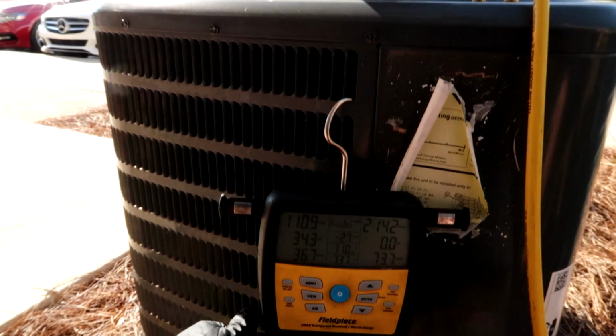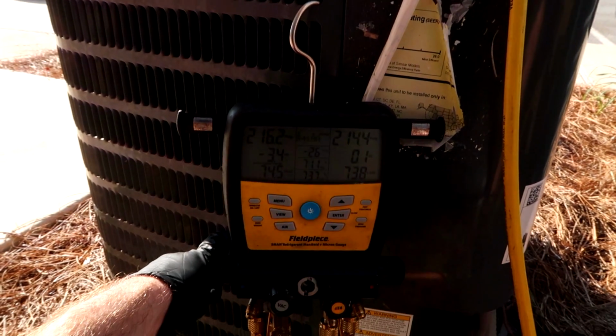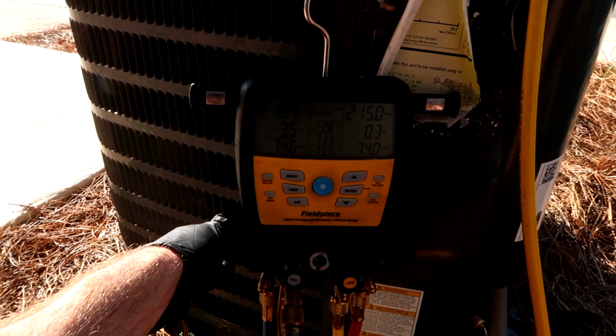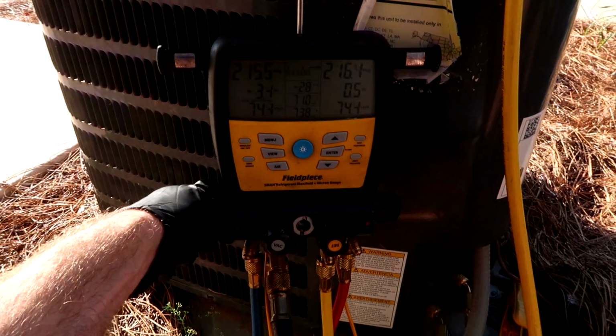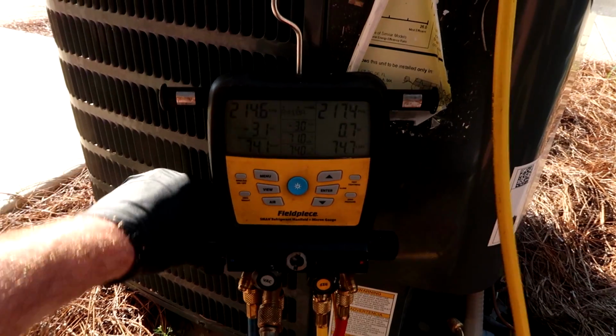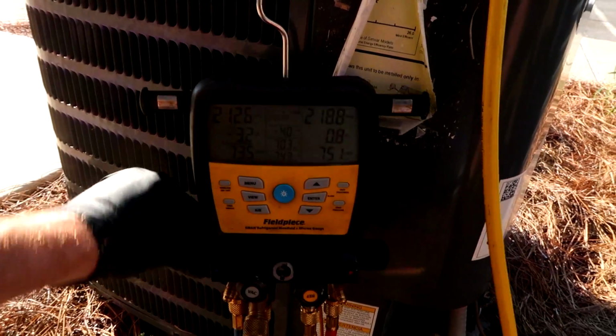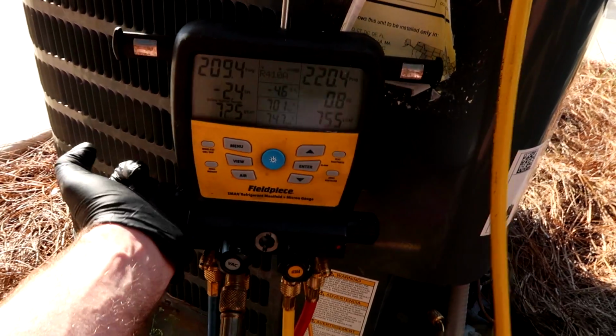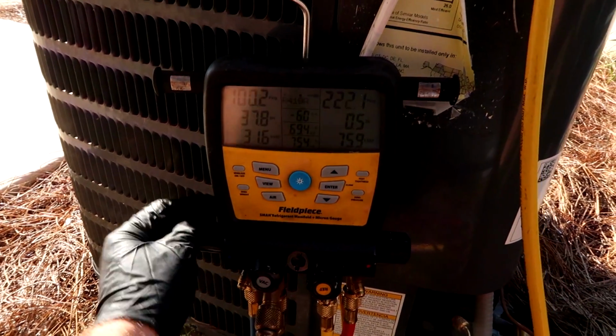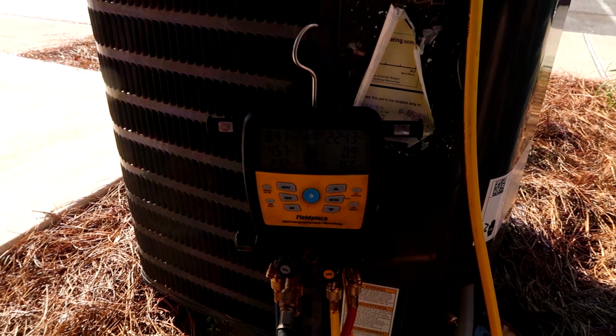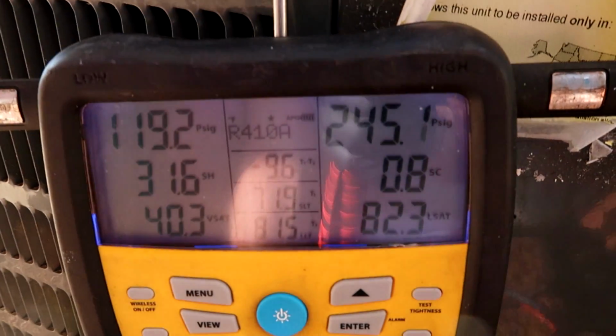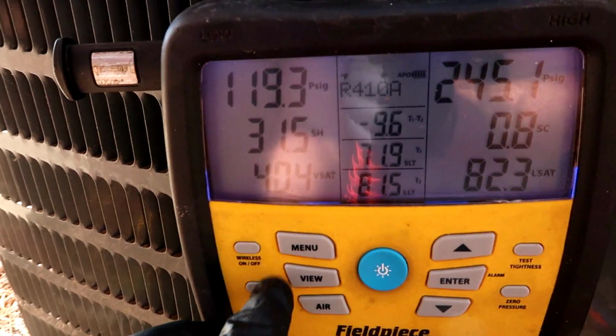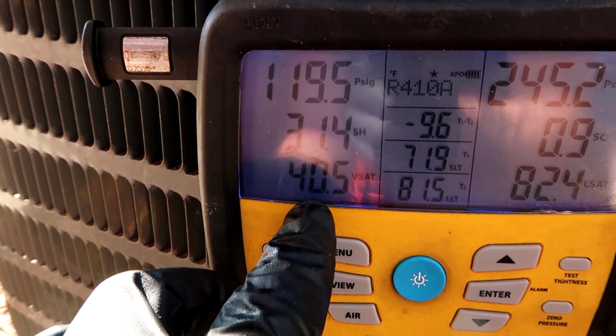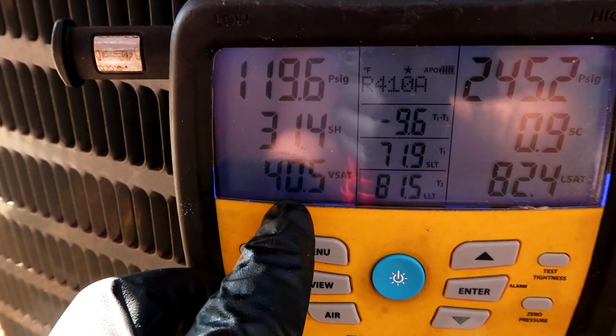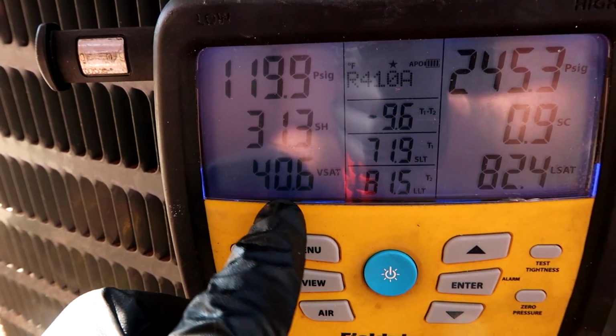I'll just start titling these videos HVAC for beginners, man. All the blow and goes I'm gonna have to do. Gas and goes. So yeah, I'll just keep popping it with refrigerant, putting refrigerant in until it gets to 12 degrees subcool. I'll be back, then we'll look for the leak. Alright, we're slowly coming up. As you can see, this is 40 degrees now. It was at 9 degrees, so we're out of danger of freezing.